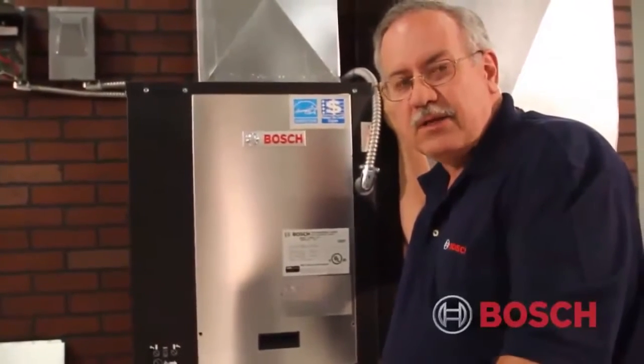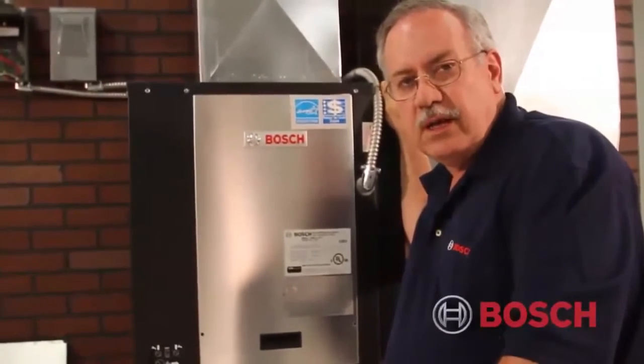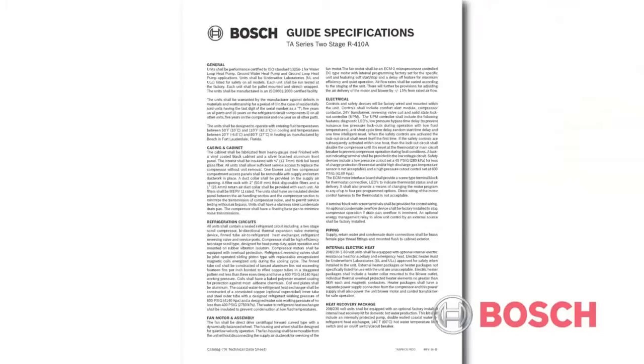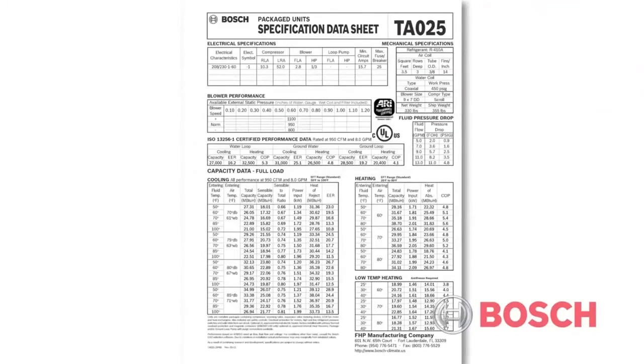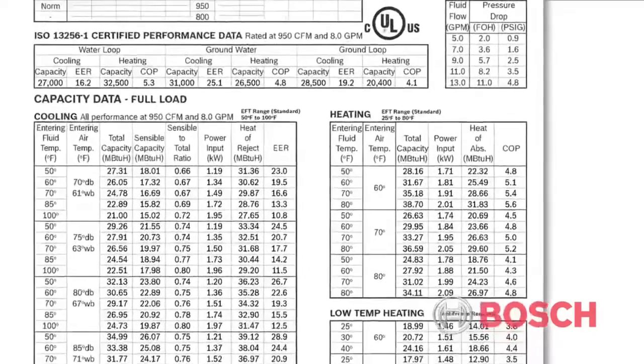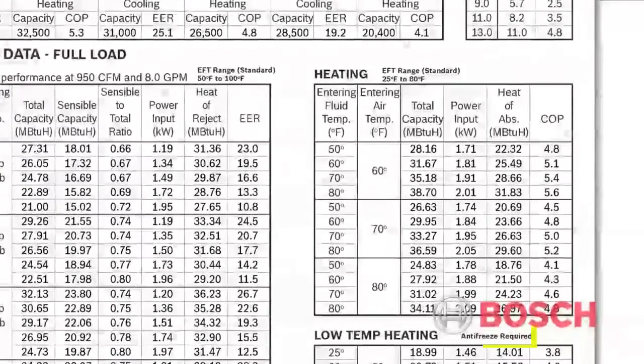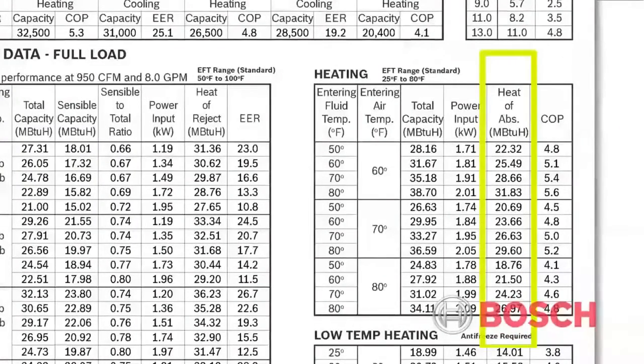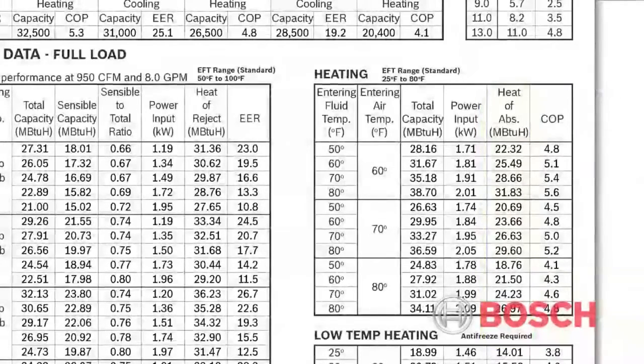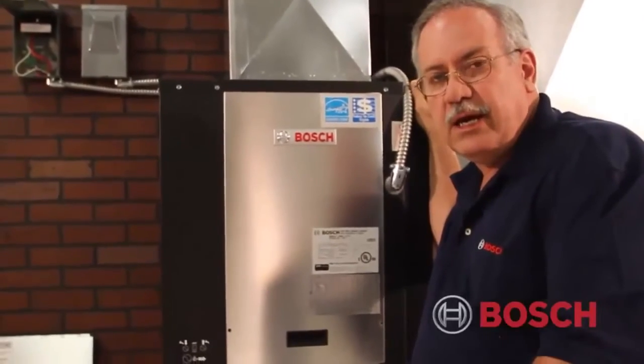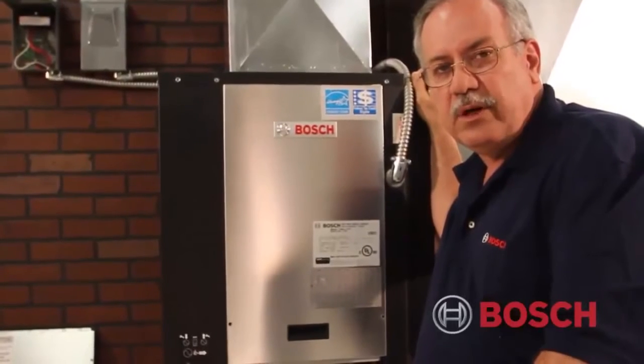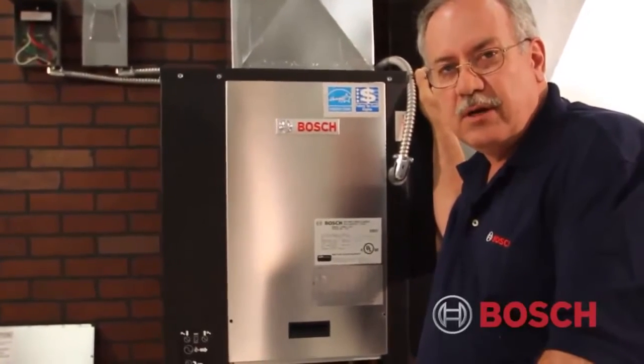Now, if I'm checking the system in the winter and I want to determine the other side, that would be referred to as heat of absorption. Some people call it heat of extraction. In that particular case, we're absorbing the heat from the earth into the fluid, transferring it into the refrigerant, rejecting the heat into the airstream. So in this particular case, we'll be checking in cooling, therefore we're determining heat of rejection.